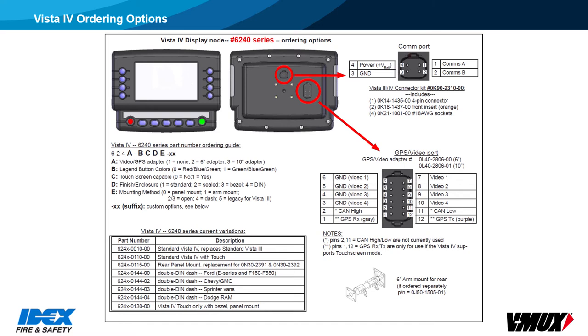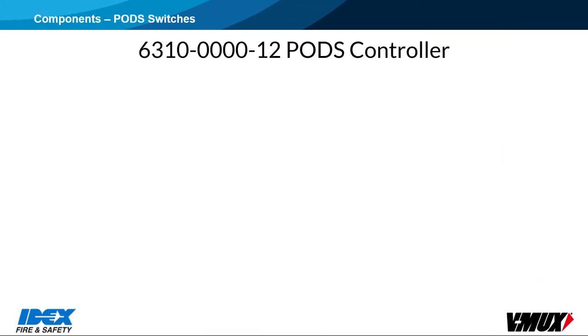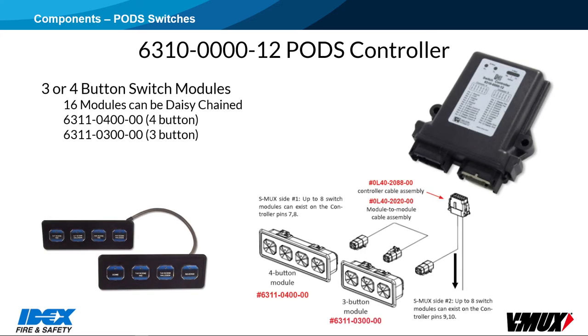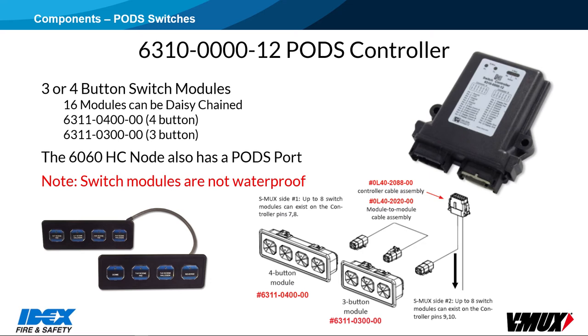A 6241 display has no video adapter cable, and a 6242 includes a 6-inch cable. The 6310 PODS controller is used to control a network of 3 or 4 button switch modules that can be daisy-chained together. Up to 16 switch modules can be controlled by each PODS controller, on a secondary network called S-MUX. The 6060 High Content node also has a PODS port, potentially eliminating the need for this controller. PODS should only be used in dry locations because they are not waterproof — water intrusion can occur at the seam where the two parts of the switch housing go together.